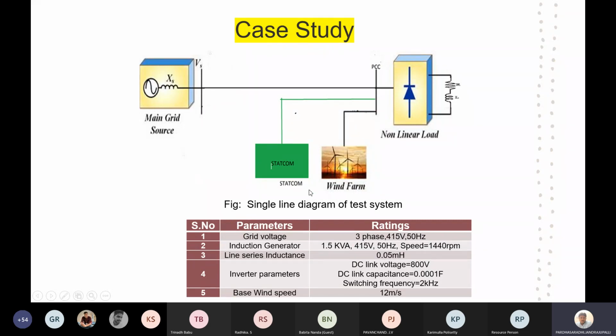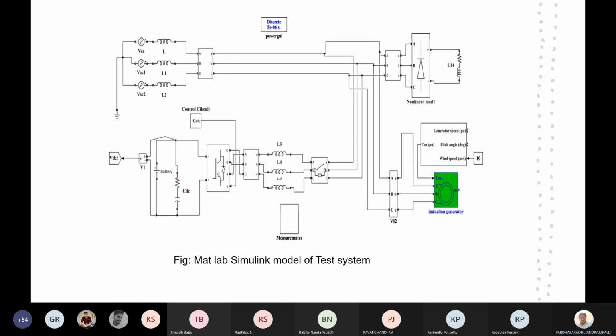To mitigate these harmonics, I have used the StatCom, which is based on a simple controller. By using this simple controlling topology, I have reduced these harmonics. Coming to the parameters of the test system, the supply is 3-phase, 415 volts, 50 Hz, along with the generator specifications. These are the different parameters of the test system.